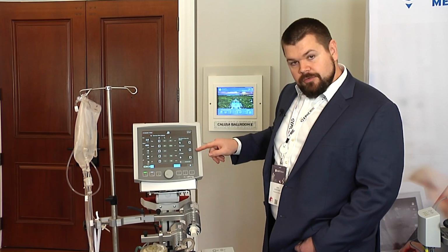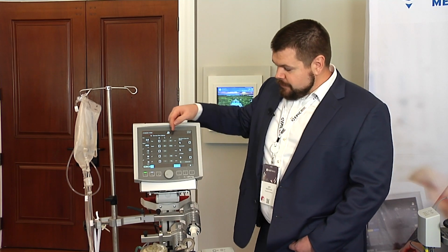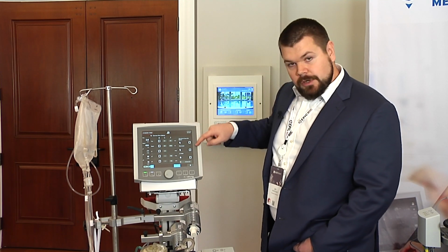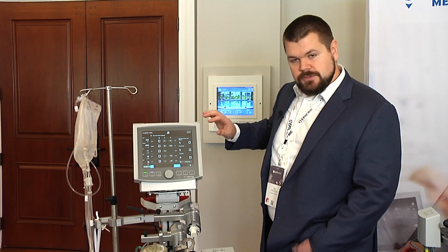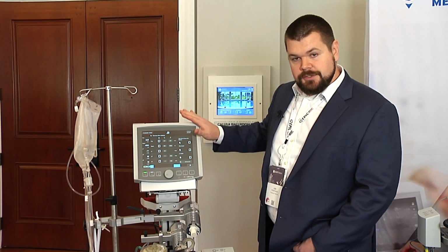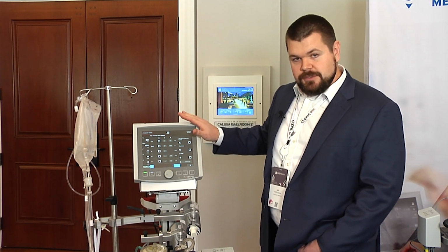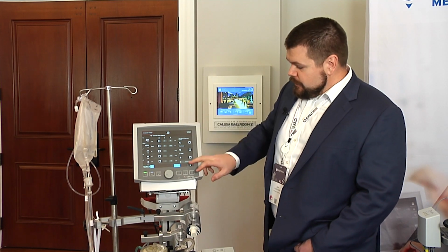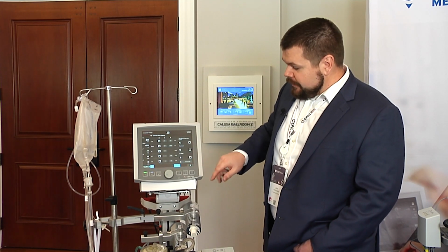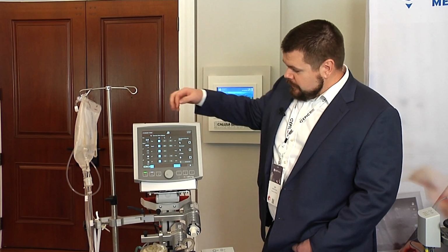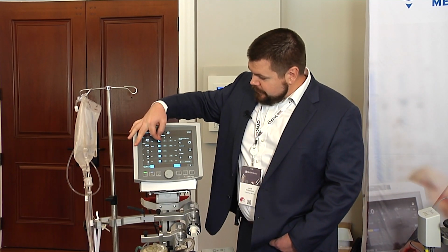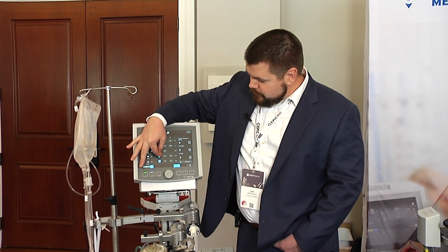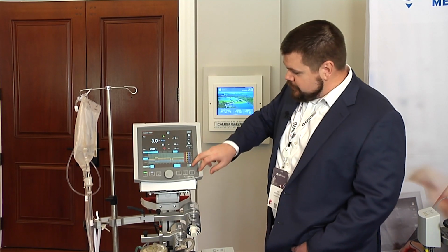One is your alarm overview. It gives you your treatment numbers, all of your alarms on one page, as well as your interventions. So this system has servo-regulated arterial bubble detection, as well as venous pressure servo regulation. You can turn all of your alarms on and set them automatically if you wish, and you can activate your interventions here on the left-hand side of the screen. So I'm going to briefly turn those off so I can show you the rest of the machine.